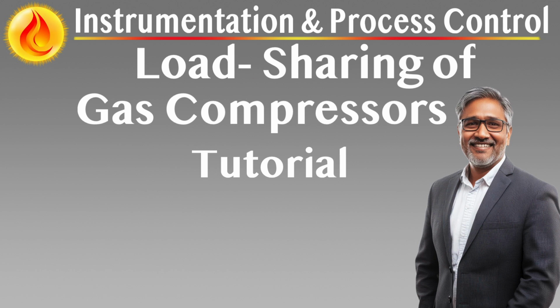Pressure override control, surge-safe stabilization during rapid or excessive pressure deviations. Overview. Pressure override control (POC) serves as a protective augmentation to the standard capacity and surge control strategies in parallel compressor systems. It is specifically designed to address fast or excessive deviations in the network's controlled pressure or flow variable, conditions that can arise during process upsets, abrupt load changes, or system transients.